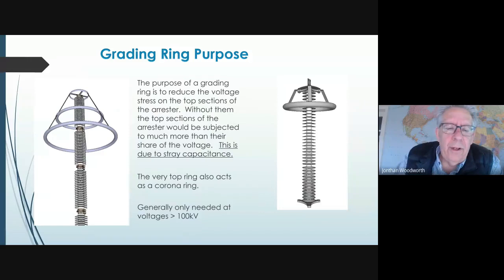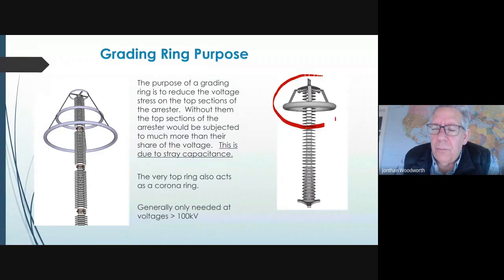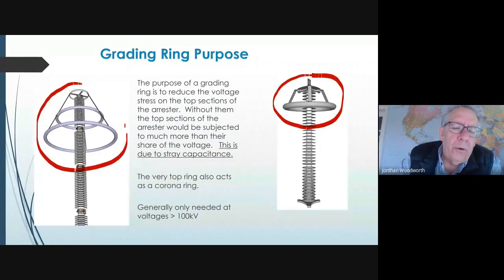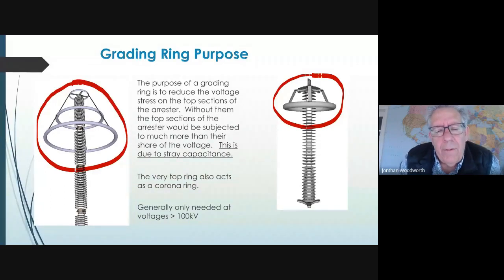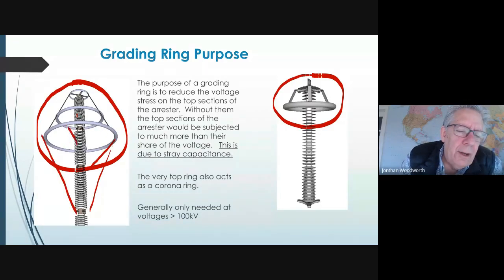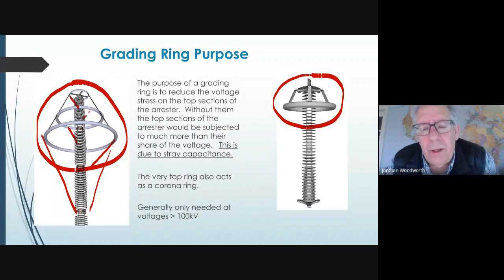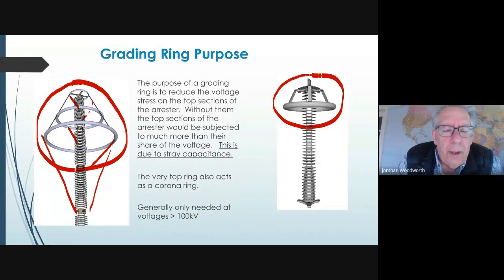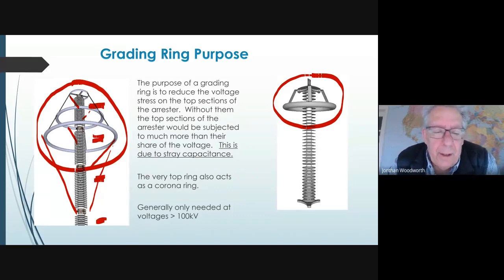You also may have seen at the top of some of these taller arrestors these big metal rings. And these are what we call grading rings, and they are there to generate a different stray capacitance to the line. This is called the grading. What it does is it equalizes the voltage along the outside of the arrestor and on the inside of the arrestor. And without it, it might overheat. So we put grading rings on arrestors. And it's really a complex topic, but I just wanted to let you know that it does exist and what they're for.